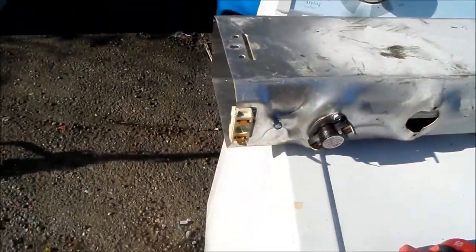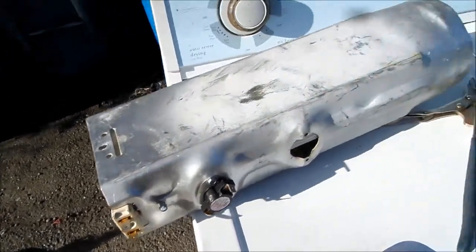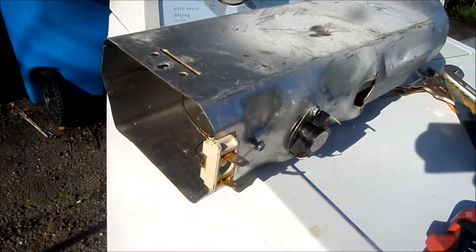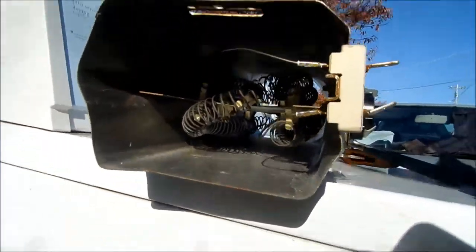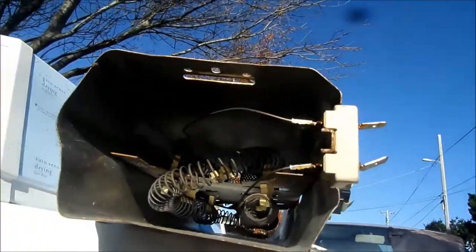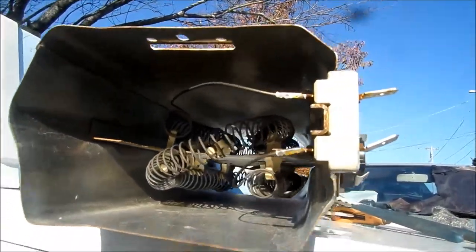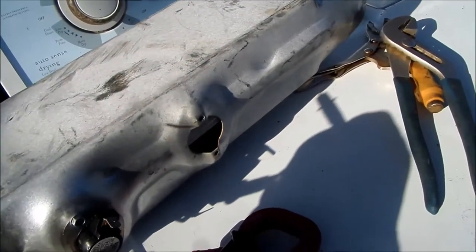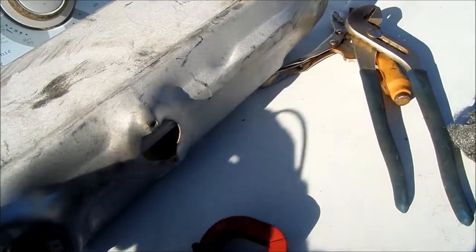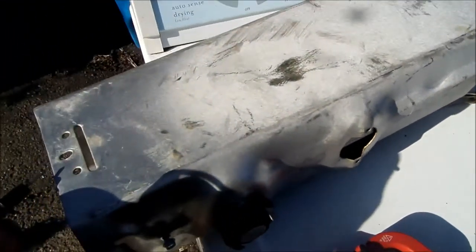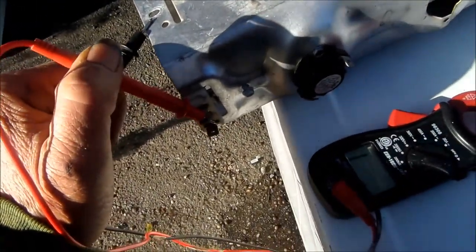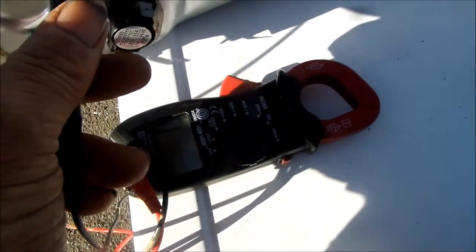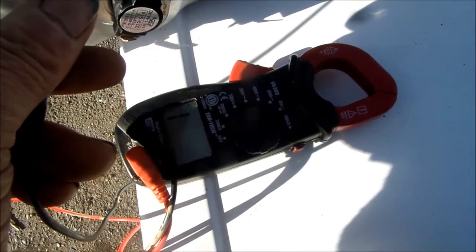Okay, before we hook this heat element up, what we're going to do is we're going to do a short test. Testing for shorts. If you look in there, we'll see that the heat element does not touch the housing at all. So we're just going to test that with a meter. Set the meter on continuity, one terminal connected and the other terminal to the ground. And we see no continuity there. So that's a good sign.